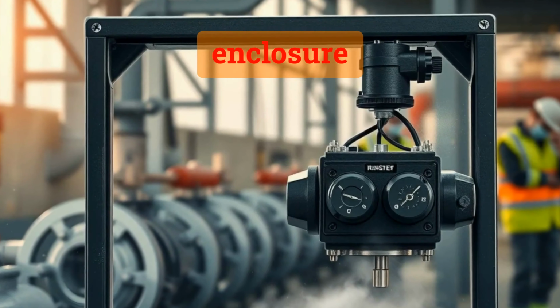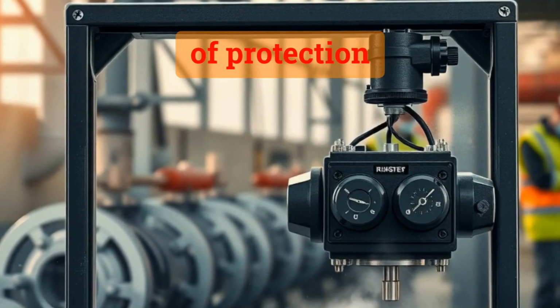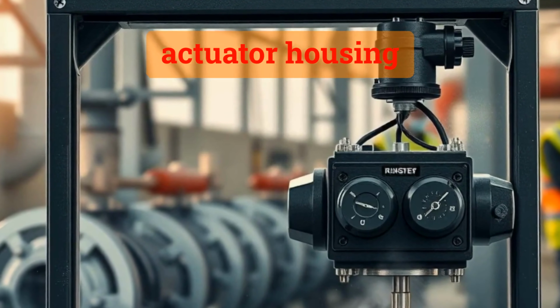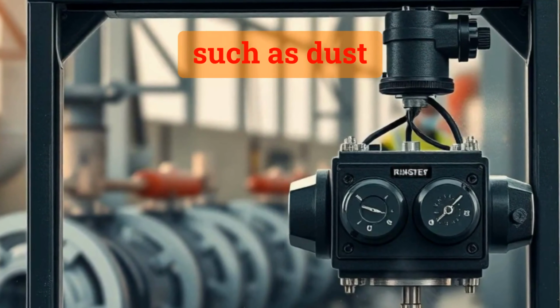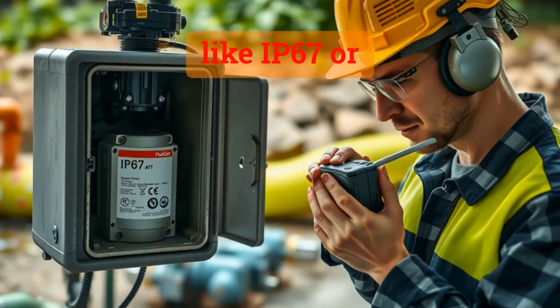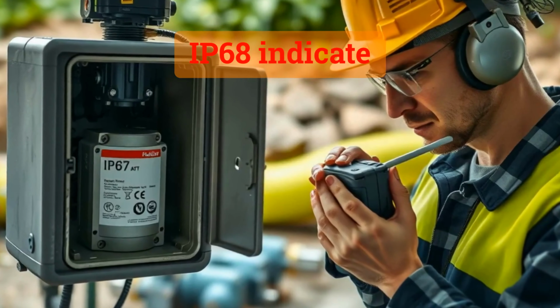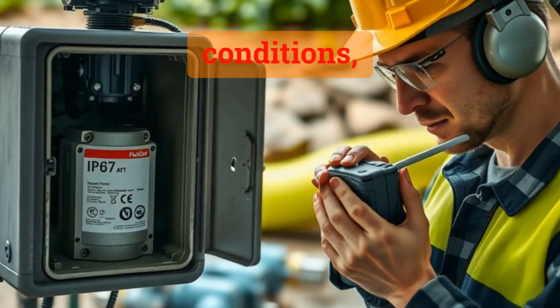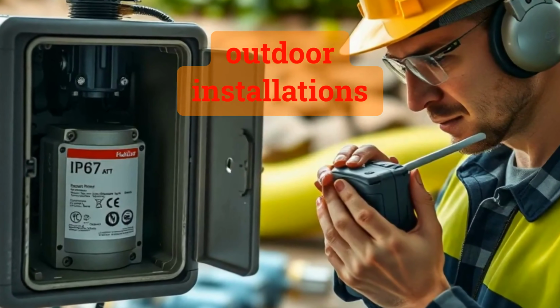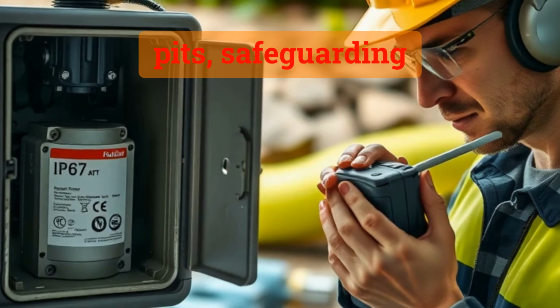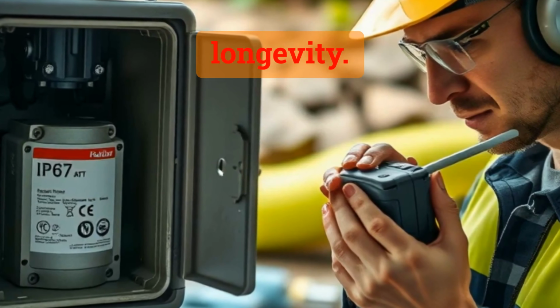Electrical actuator enclosure rating defines the level of protection provided by the actuator housing against environmental factors such as dust and water. Ratings like IP67 or IP68 indicate suitability for specific conditions, such as outdoor installations or underground pits, safeguarding the actuator's performance and longevity.